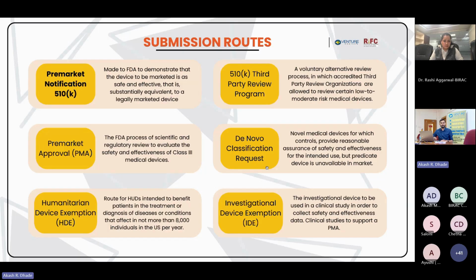Then there is the de novo classification request. If you think that your device, your technology, does not have any similar devices in the market and it is very novel, a novel solution given for certain medical conditions, then you go ahead and apply for de novo classification. This way, you can prove that your device does not fall under any category. There are no recognized standards, and the FDA can guide you through this process. The advantage of going de novo is that your device will be first of its kind in the US FDA market, and that creates a huge opportunity. However, proving the novelty also becomes a burden for manufacturers sometimes, and that can create hurdles if you don't have sufficient funding or sufficient timeline to get into the market, right?